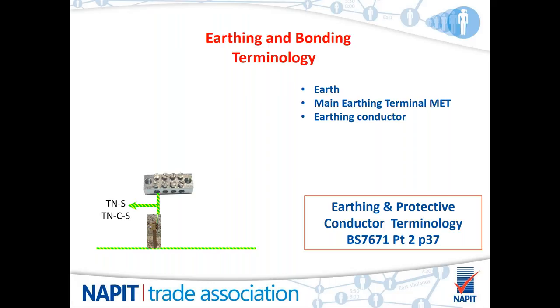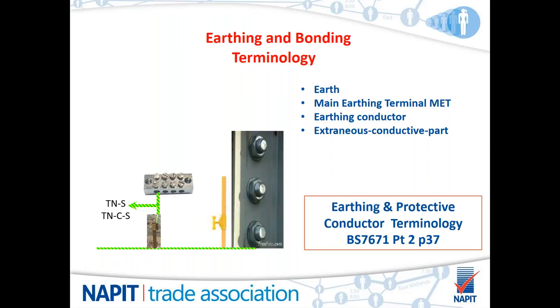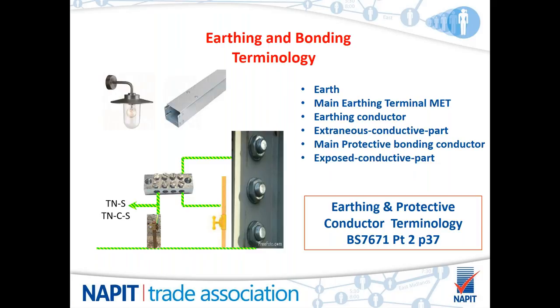This earthing conductor then goes to the point of earth, either the TNS system or TNCS system provided by the distributor, or the earth electrode for a TT system. Also now we have the extraneous conductive parts shown: steelwork within the ground, water pipes, gas pipes entering the building, and these all need to be protectively bonded back to the main earthing terminal. What we have here is the class 1 equipment, the metal exposed conductive parts. We've got a metal light fitting, we have a bit of steel trunking, and they would need a CPC connecting each one of those from the main earthing terminal to those points.